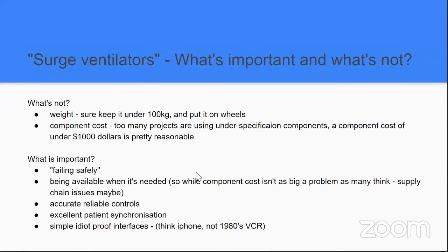What's important in a surge ventilator? A couple of things we can discard immediately. Weight is not really a problem — we don't need lightweight ventilators. We've already got self-inflating bags for short-term transport. We don't really need portable ventilators — if it's heavy and has a car battery, we'll put wheels on it. Hospitals have good floors and are used to heavy equipment. Most ICU ventilators come in over 50 kilograms. So weight is not a big problem.